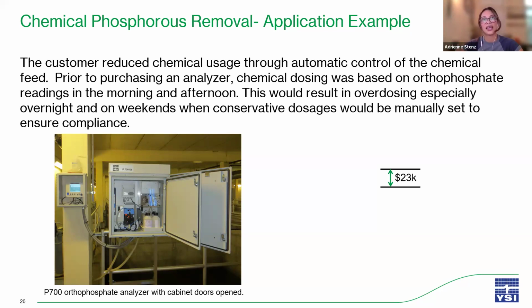So before installing the analyzer, they would spend almost $100K per year on ferric chloride. The plant implemented an orthophosphate analyzer to automatically control dosing of the chemical. And after the first year with the analyzer, they saved about $23,000 on chemicals, which was about the cost of the analyzer. So they saw an ROI within 1 year. And since implementing this analyzer, they have spent about $60 to $75K per year on ferric chloride.